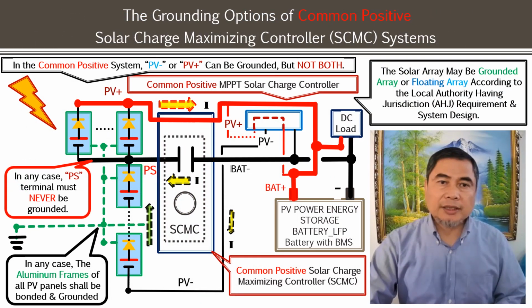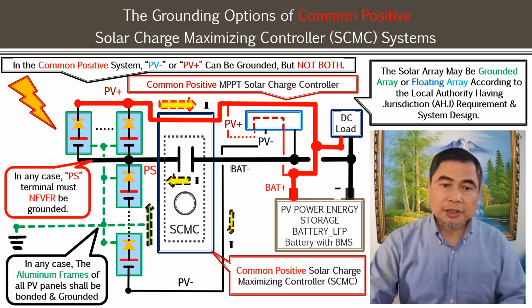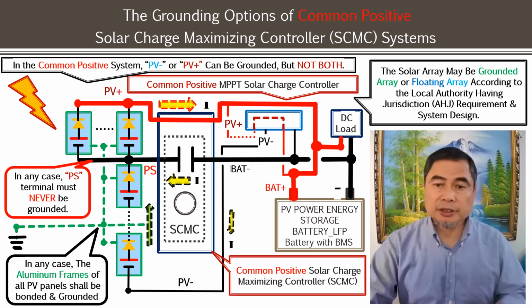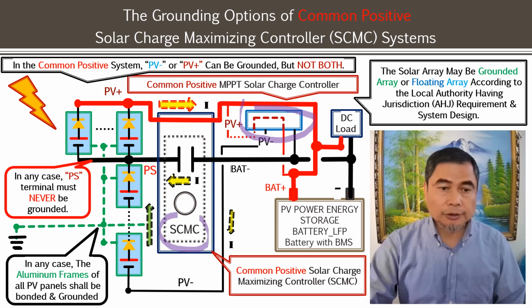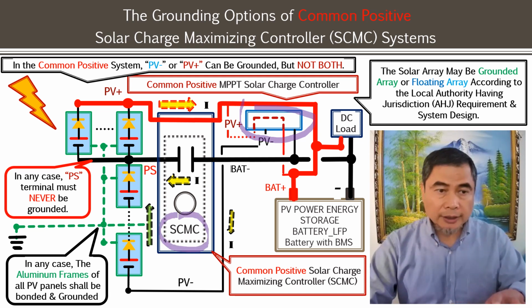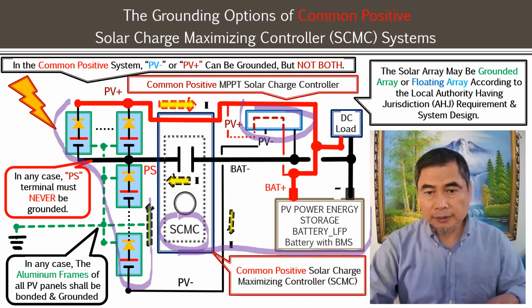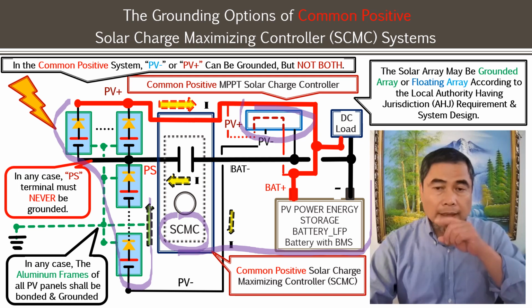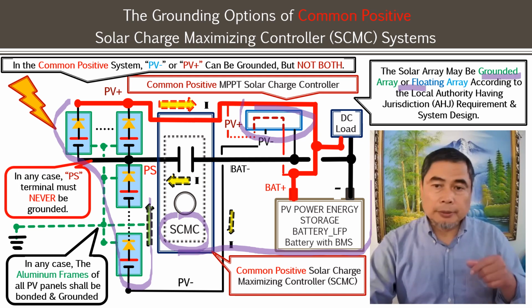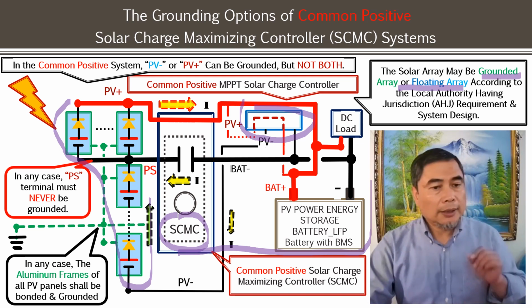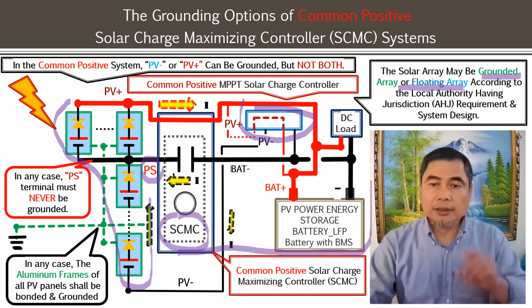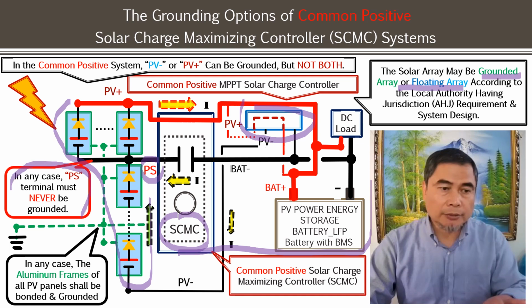We talked about a common negative system, what can be grounded, but this is a common positive. This MPPT solar charge controller system is also positive, so they all together form a common positive array configuration. The solar array here could be grounded, or it could be a floating array. We mentioned that according to the local authority having jurisdiction, AHJ requirement, building code requirement, whatever it is, just remember that the PS split wire never gets grounded. It cannot be grounded.